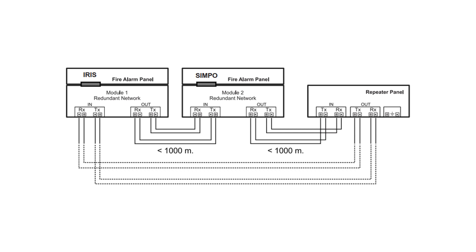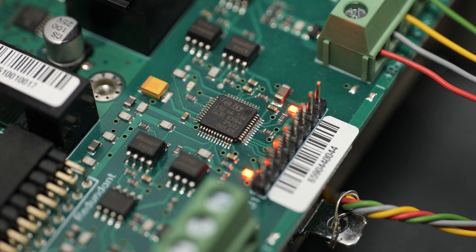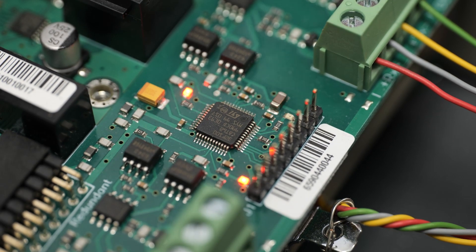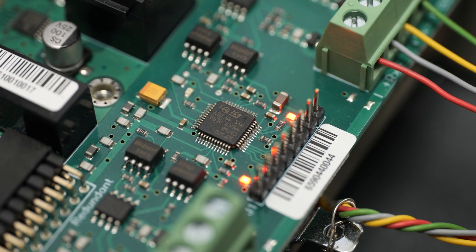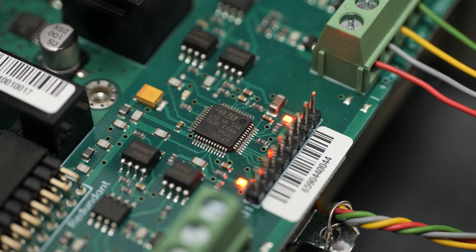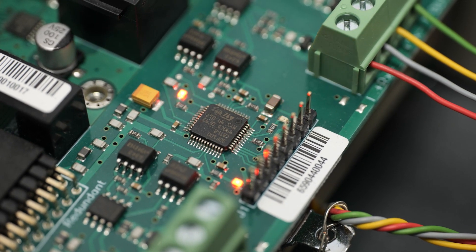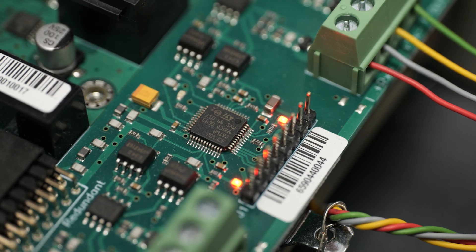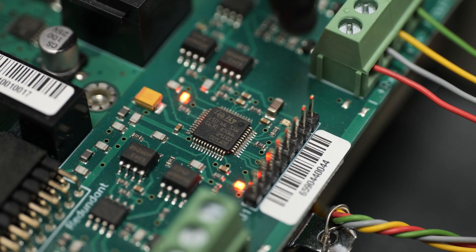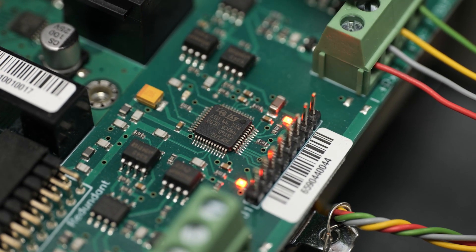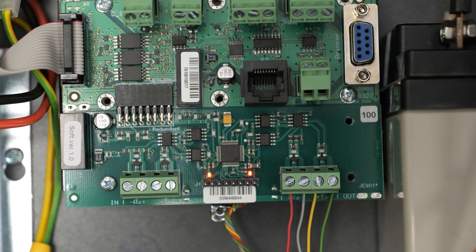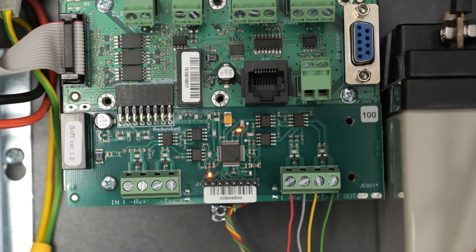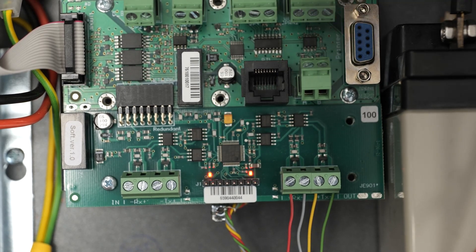It is important to know that the maximum cable length between two RS485 network modules is 1000 meters. There are also three LED indicators used for connection quality status. The one on the top is for connection between the redundant module and the panel itself, while the other two LEDs indicate the connection with the other panels in the network. A blinking LED means the connection is good, and if the LED is continuously lit there is no connection established.